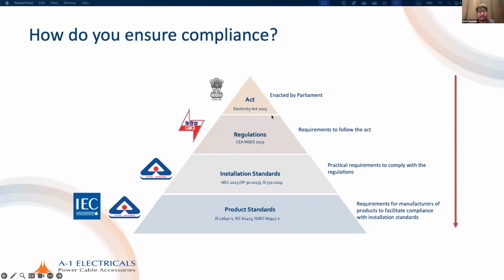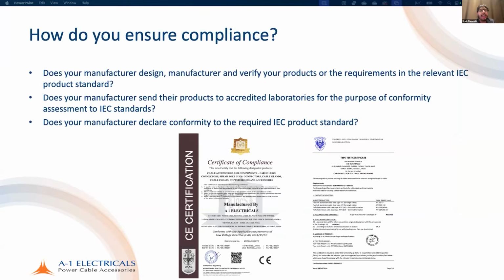Of course, we are not manufacturers, right? As a designer, as a consultant, you're not a manufacturer. How do you select a product? That is a big question that arises. The answer is you need to receive documentation from your manufacturer to this effect. So you have to ask your manufacturer these questions. Do you design, manufacture, and verify your products according to the requirements in the relevant IEC product standards? Importantly, design, manufacture, and verification. Does your manufacturer send the product to an accredited laboratory for the purpose of conformity assessment?